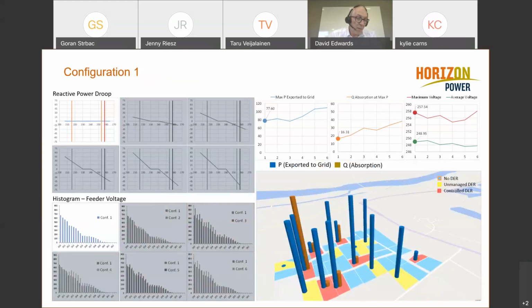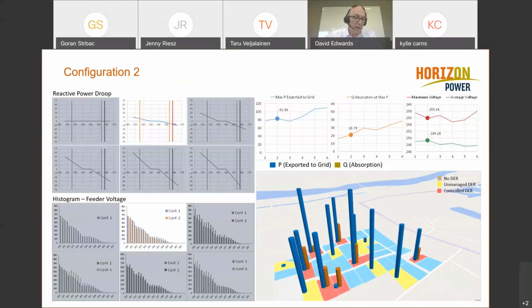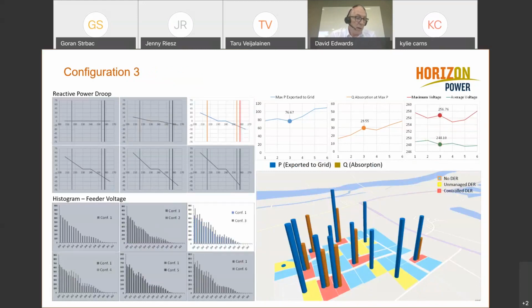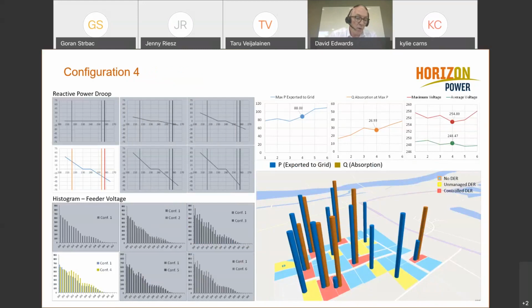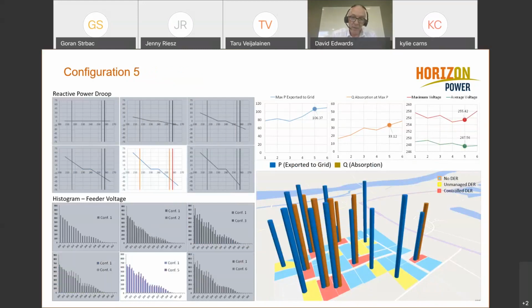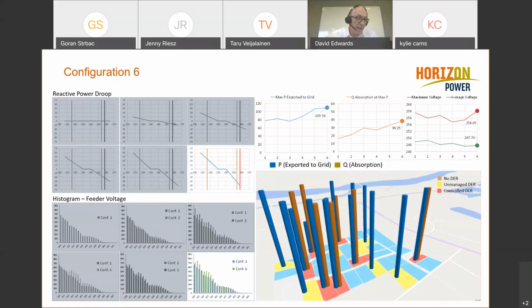So what you'll see in the following visualization is that the inverters under control actually do a very good job of importing reactive power to reduce voltage. But at the same time, they create an operational advantage for all of the uncontrolled PV systems, who then raise the voltage back up so that they can export more power. The end result is a negligible reduction in the maximum voltage on that feeder, but an appreciable increase in the amount of renewable energy exported onto that feeder.